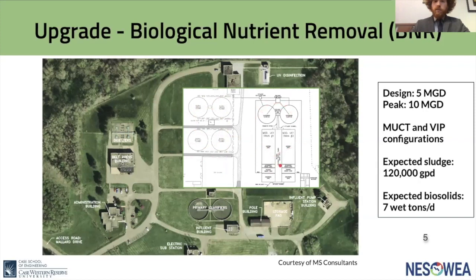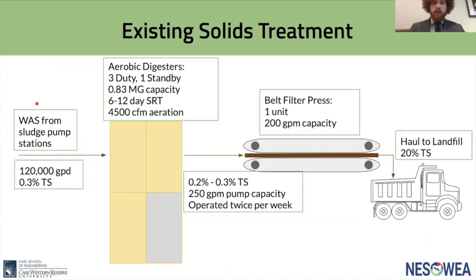In this open field, the biological nutrient removal facility will be built and will produce activated sludge. We expect that 120,000 gallons per day of sludge will need to be wasted to the digesters, and with the current system, we expect seven wet tons of biosolids produced every day. Unlike the old system, the upgraded facility will only produce waste activated sludge and no primary sludge. Due to this change, models of the plant predict the total solids concentration will be reduced by a factor of four, to only 0.3% total solids.